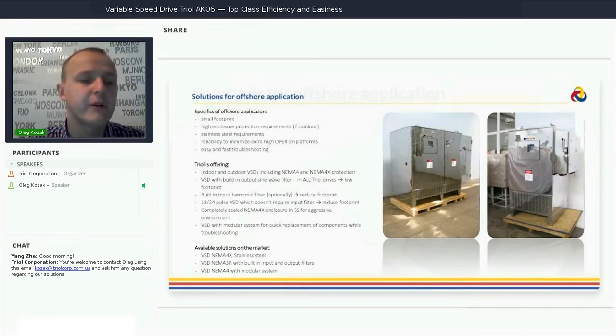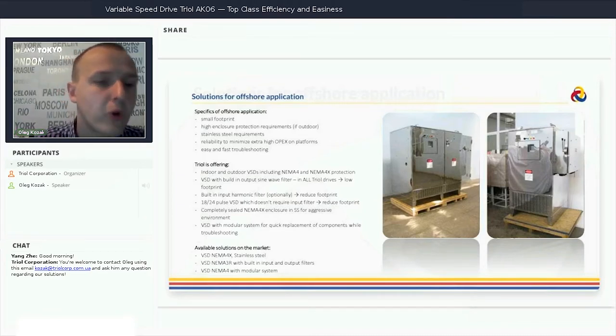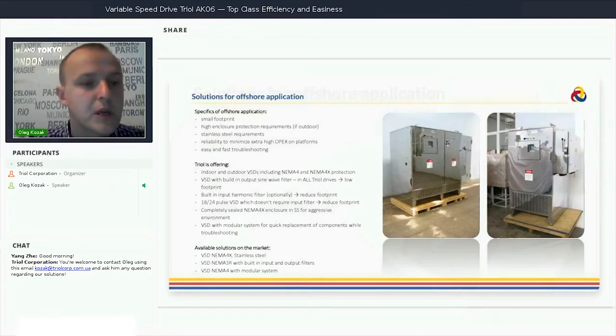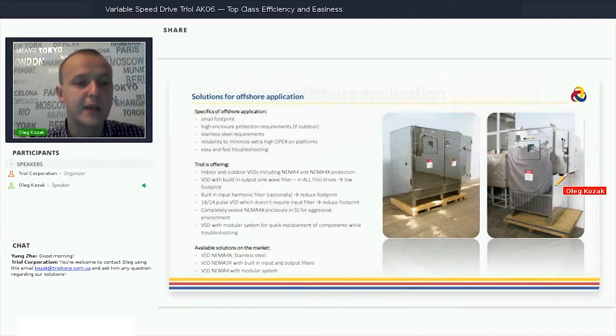We have lots of positive references offshore as well as onshore. We have a modular system for fast troubleshooting. All our parts, like inverter modules, capacitor modules, and DC link modules, are separate modular parts which are easy to replace. You keep stored spare modules, and in case of any failure, you just plug and play. Remove the inverter module and put in a new one. That's all. It takes 20 minutes to replace and continue operation.